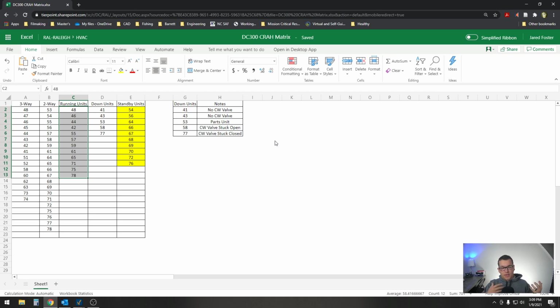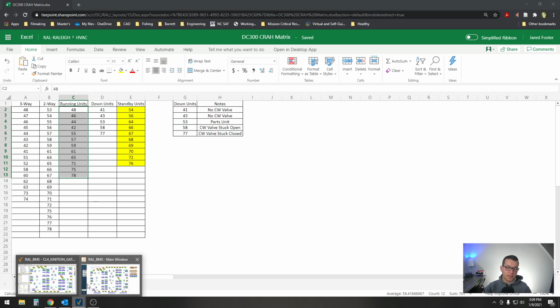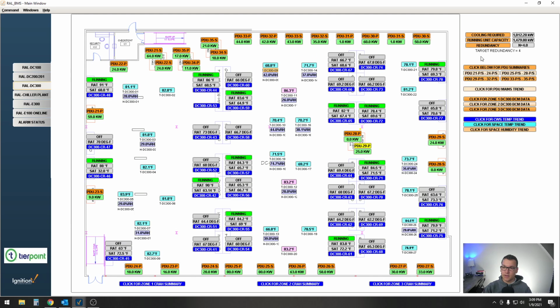Going back to the customer thing, we now know we've progressed to a certain point in the project where it's actually a happy medium between efficiency and performance, so we can go turn some units back on and leave them as standby units. From an engineering perspective, we should never need them because there's already 4 units of redundancy built into this running number, and I'm sure you've seen this target redundancy number.